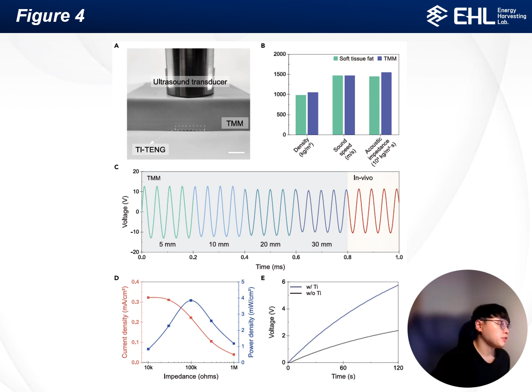Since the purpose of this research is to develop acoustic power transfer systems for implantable devices, a standardized setup for the characterization of device output that is similar to the in vivo environment is important. So we propose a tissue-mimicking material, and using this environment, we measure outputs over depth, power density over impedance, and capacitor charging performance. We found that the titanium-packaged devices had a 310% power density compared to unpackaged devices, which demonstrates the importance of our technology.